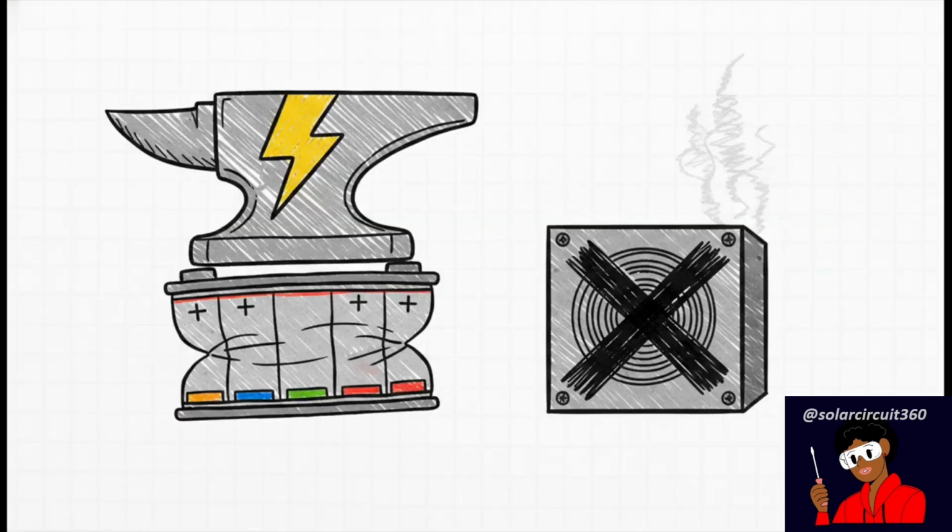And here is the absolute kicker: transient voltage collapse. When the inverter yanks that massive current, your battery's voltage naturally sags. If it dips too far down during that violent inrush, it triggers the inverter's low voltage cutoff. The inverter just shuts down to protect itself. This hidden transient voltage sag is the actual culprit behind your 5 kilowatt inverter failing. It's not that your inverter couldn't handle the watts, it's that your battery voltage completely collapsed under the brutal, sudden strain of those locked rotor amps.